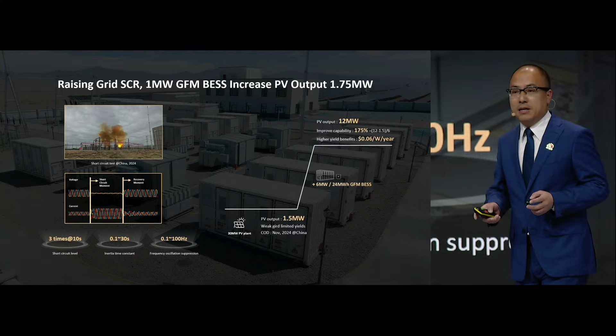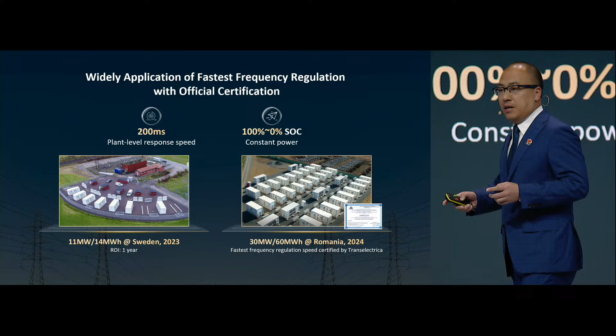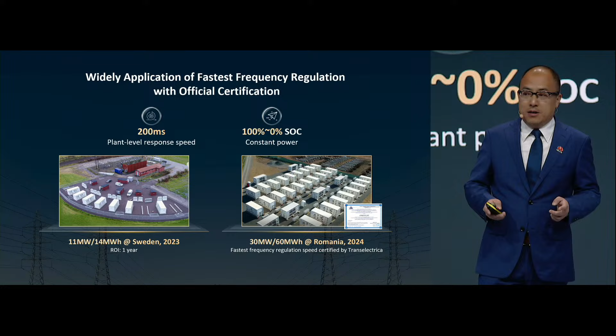In terms of primary frequency regulation, Huawei grid-forming BESS can achieve a rapid response and power output within 200 milliseconds at the plant level. This solution has been widely used. In 2023, Huawei helped a customer build a frequency regulation ESS plant in Sweden, and the payback time is only 1 year due to the outstanding performance. And in Romania, Huawei BESS solution is the first one certified by the local TSO because of the fastest response.